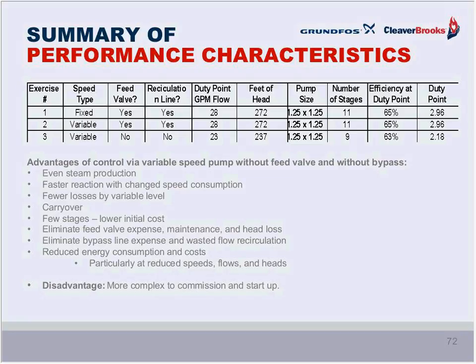Now, these are all the same 1 1/4 inch by 1 1/4 inch pumps, but number 3 uses only 9 stages versus 11 for the former 2. Now, the duty point efficiency is slightly lower on the 9-stage than on the 11-stage pump. But when you run the calculation, the total brake horsepower load for number 3 is significantly lower than numbers 1 and 2 because there's less flow and less head required.